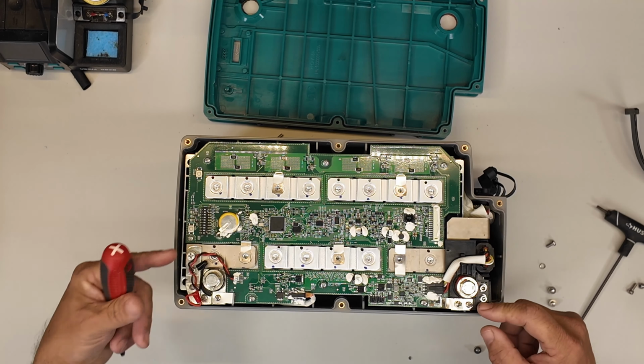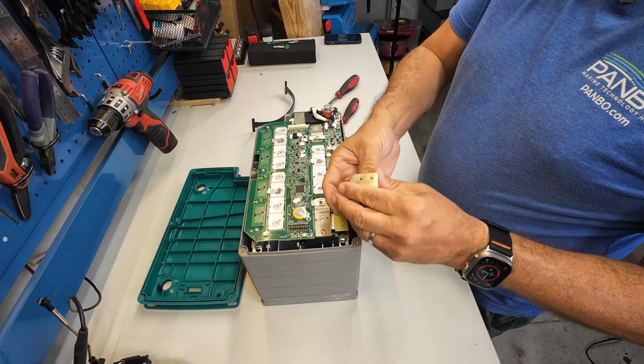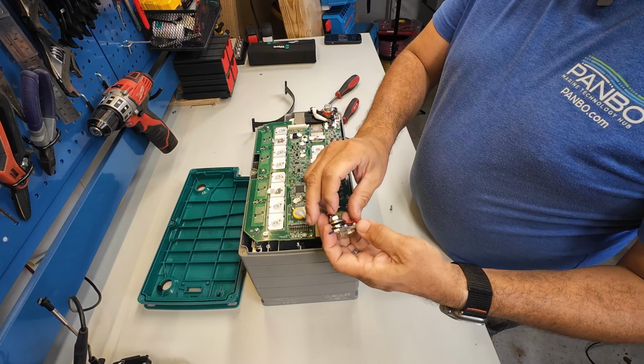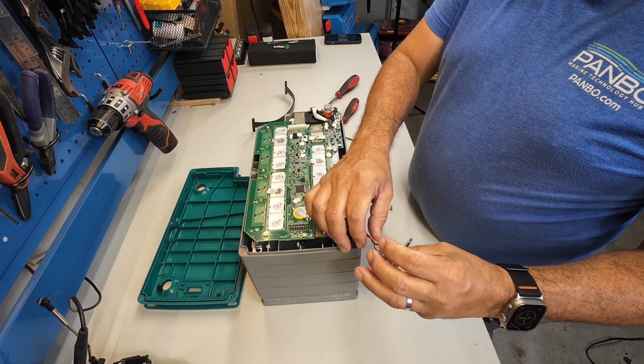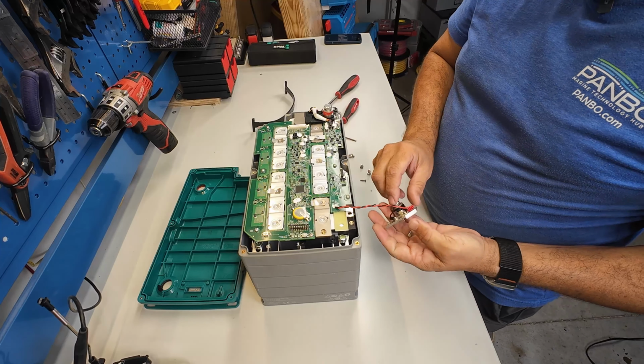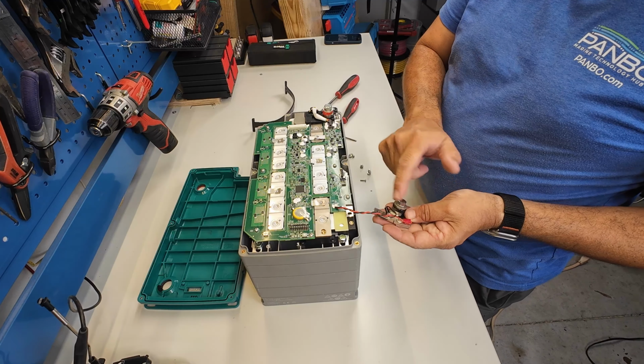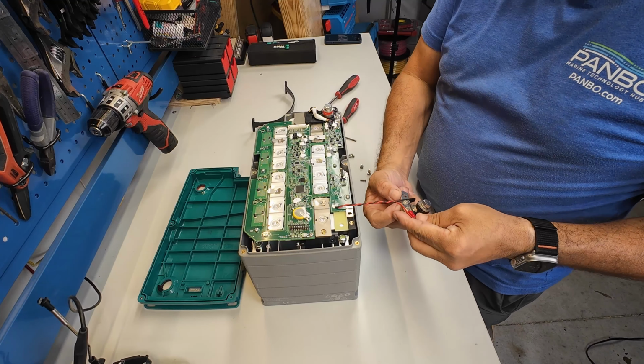Let's loosen that guy up. So right here we have our negative connection, and I see these wires tells me that this is our shunt, right? Because they're measuring for voltage drop across the shunt, and the little notch out of there makes me think that's a calibrated piece of metal with a predictable voltage drop based on current. So that's in place there.